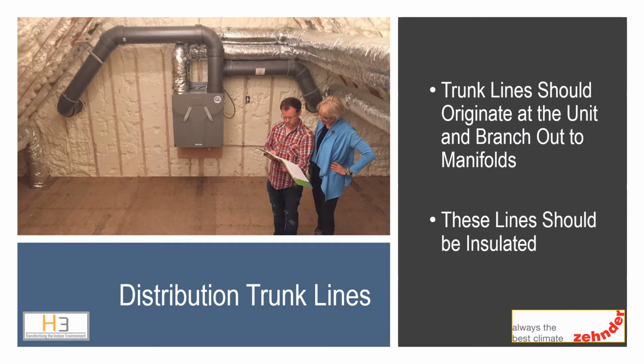Trunk lines deliver the air to the manifolds and sound attenuators. Trunk and branch ducting should be insulated. These larger ducts deliver air better over longer distances than smaller tubing. This means that a unit in the basement might need a trunk line run all the way to the second floor to minimize static pressure. It would then be connected to manifold boxes and smaller tubing running to register boxes mounted in ceilings, walls, or floors.